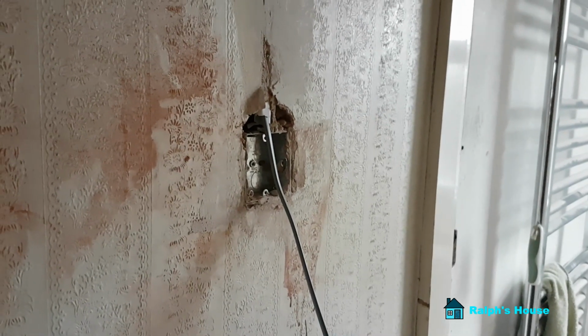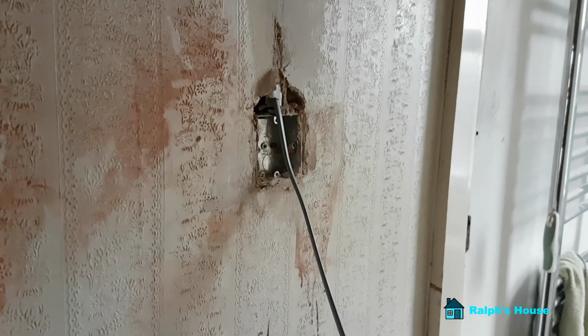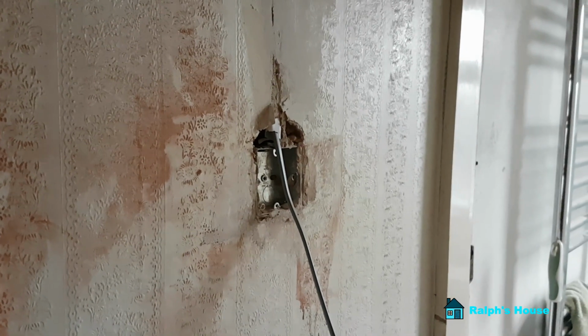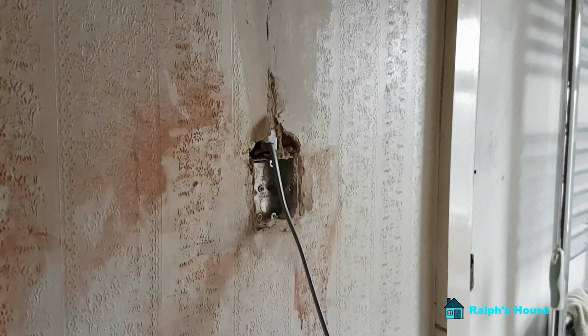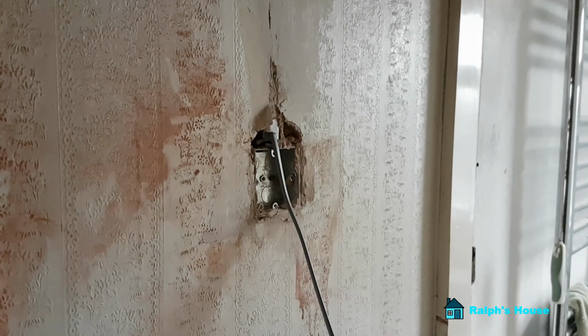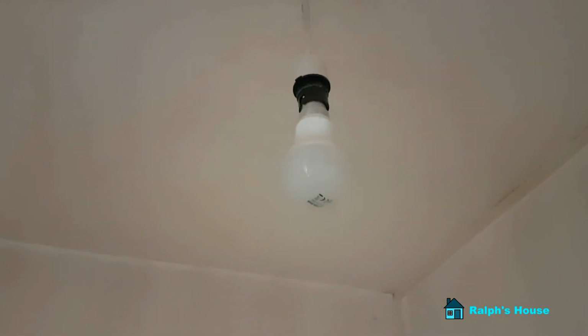I can almost do that in the dark actually, but can't do all this stuff when it's getting darker. So I'll get the switch wire in. That's crucial. I've got to get that up to the loft. So 1 live in, 1 live out to the next light, 1 to the switch, and 1 to the light bulb itself. So that's 4 of them in all. On this one, I'm going to make sure they all terminate in the ceiling rose. I'll leave plenty of slack on it, in case I decide to dispense with that and have some other kind of lighting up here. But at the moment, I just want to get the lights in.